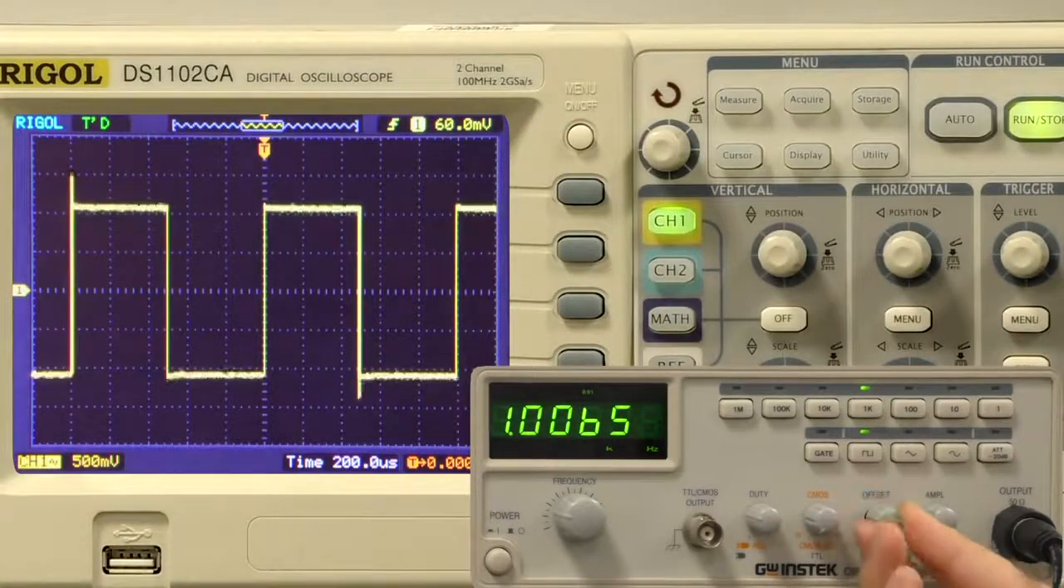This button allows you to see the offset. If I change this to AC coupling, twist it once, press it in, and twist the offset again, I'll close off the menu. Adjusting the offset won't do anything to the waveform as it's simply removing the DC component.